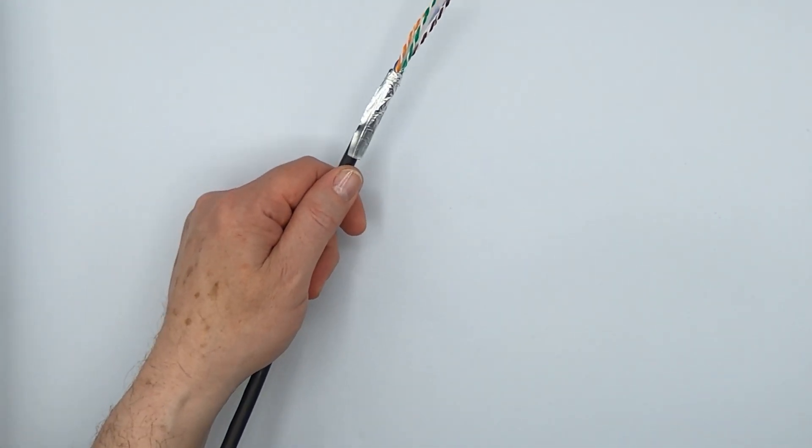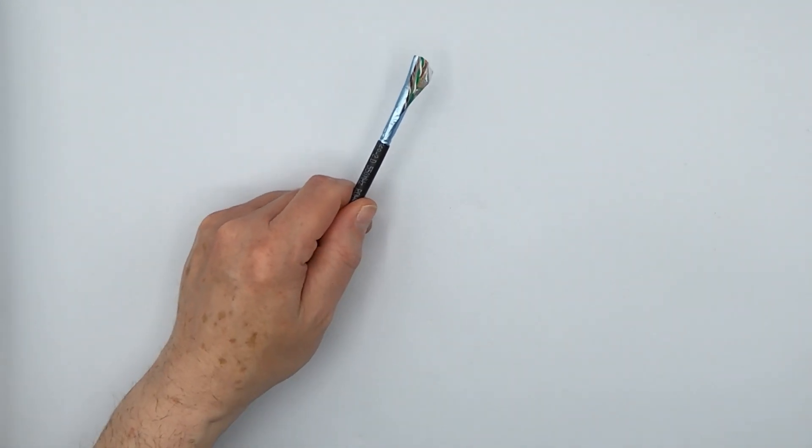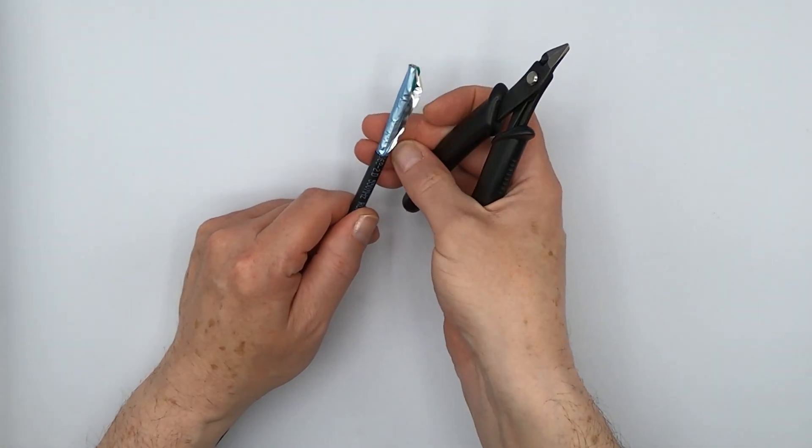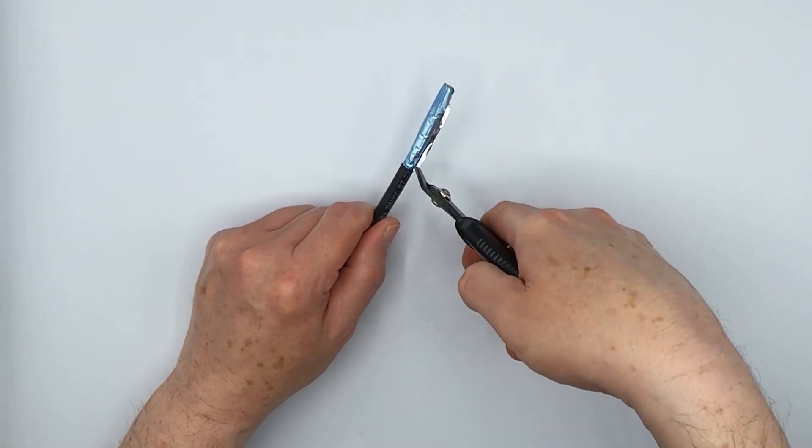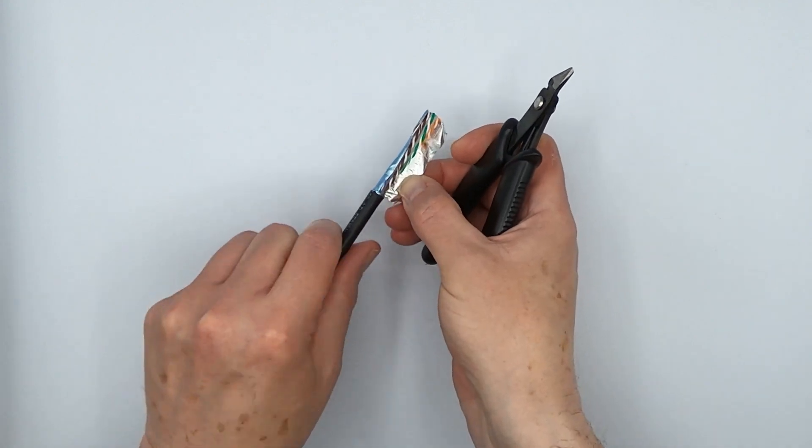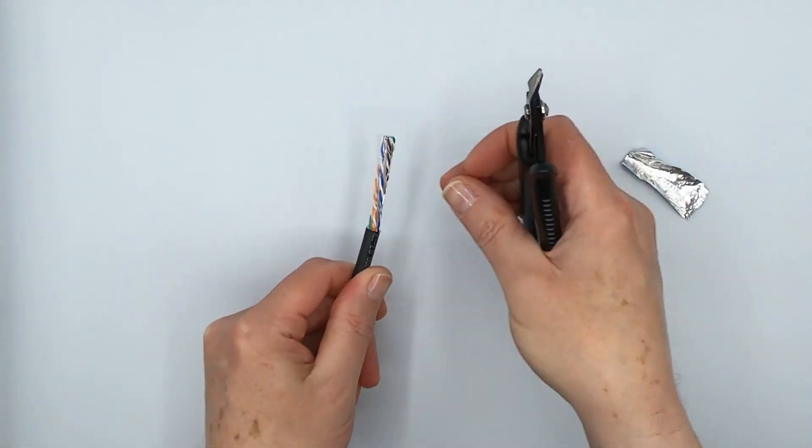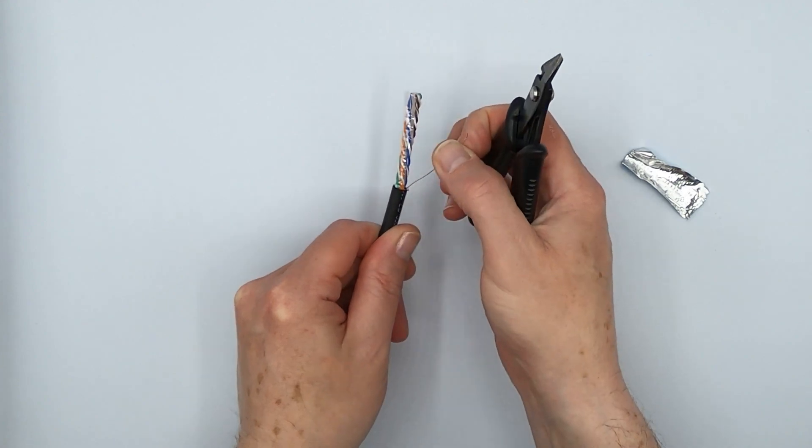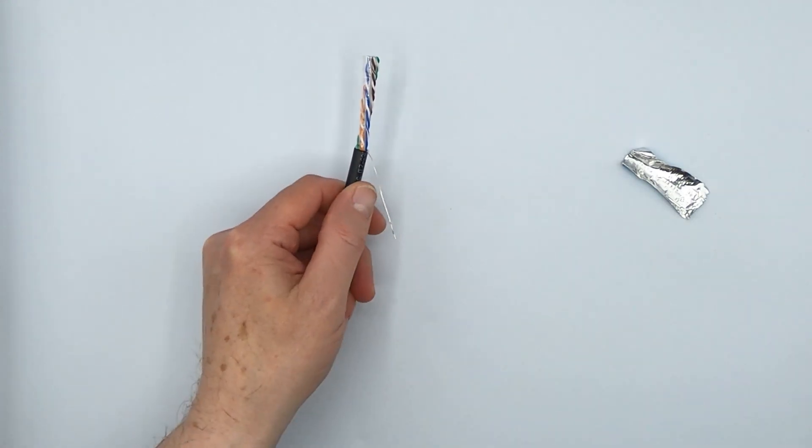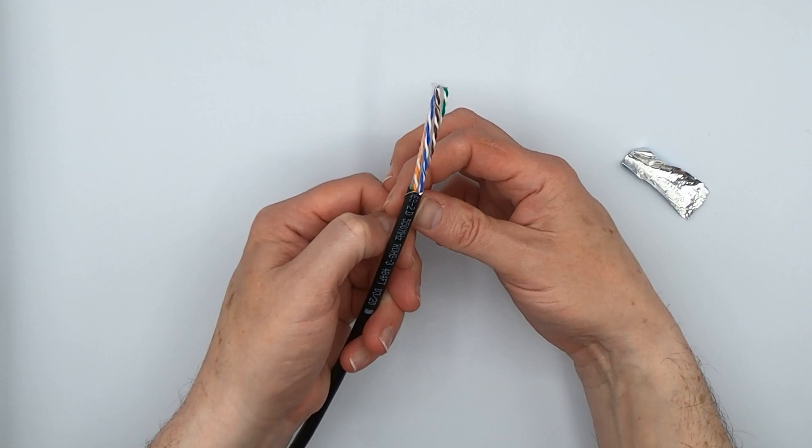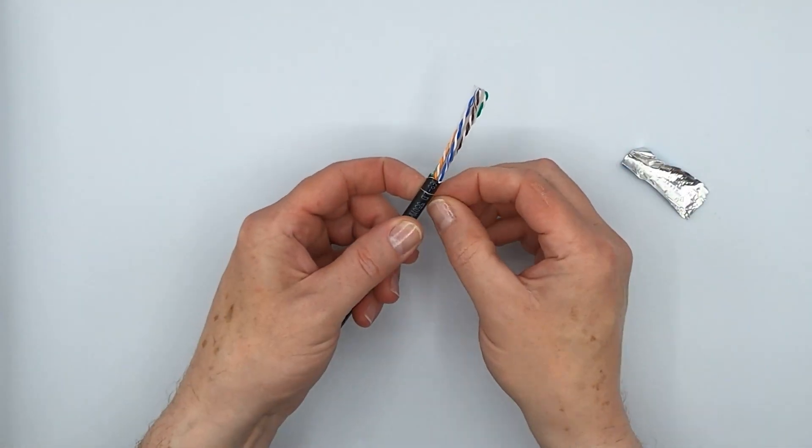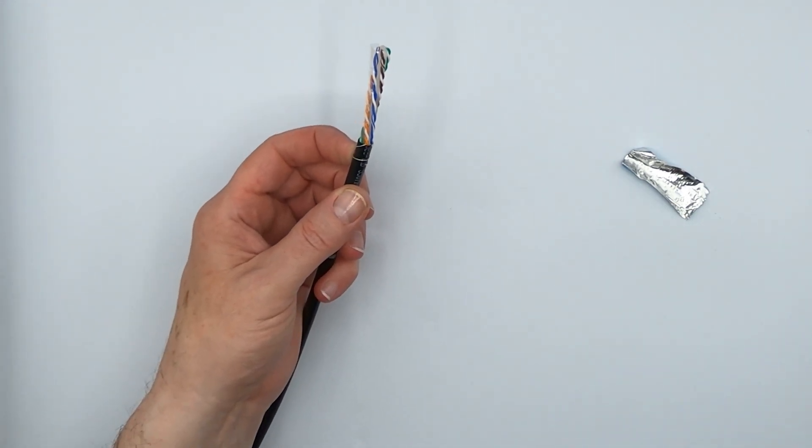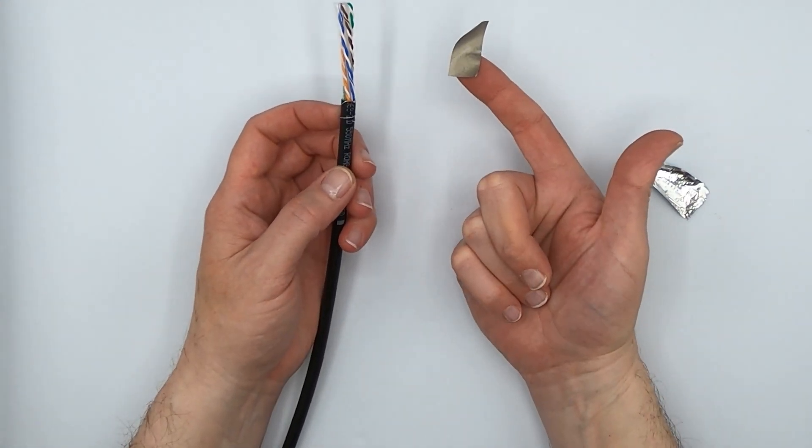Instead, why not rely on something that you can come back here after you've got your cable stripped. You can then make a small nip here in your cable shield, peel it right on off intentionally. You've got this drain wire. And then you can take your drain wire and then fold it backwards and wrap it around your cable jacket.